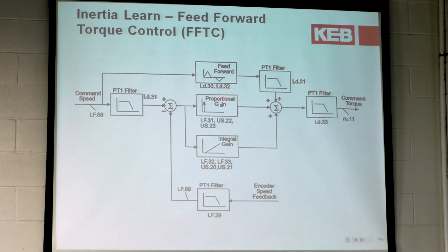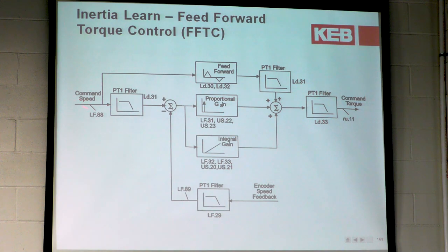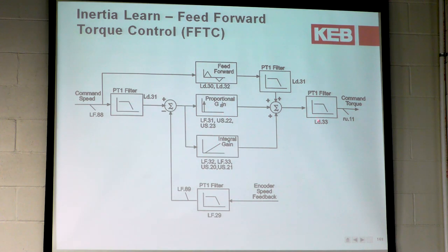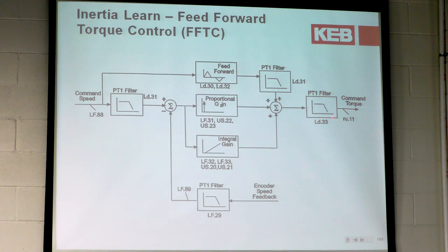Picture this diagram without the two feedforward boxes at the top — just the proportional gain and integral gain. During a run, you have a command speed that goes through an internal drive filter (LD 31), then to the gains, then out to an output filter, and finally out as the command torque. On your first speed command, there isn't going to be any error because we don't have any feedback coming back yet — say we want to go 50 feet per minute, that's what's being output.